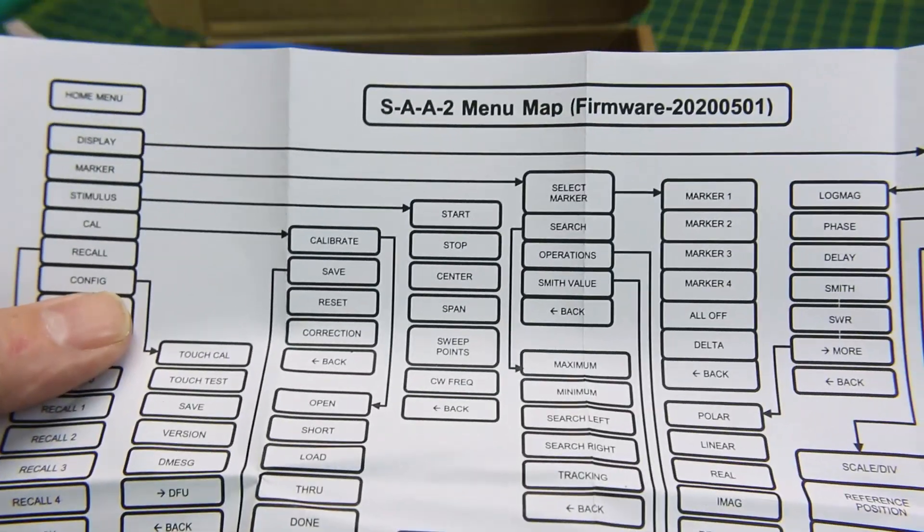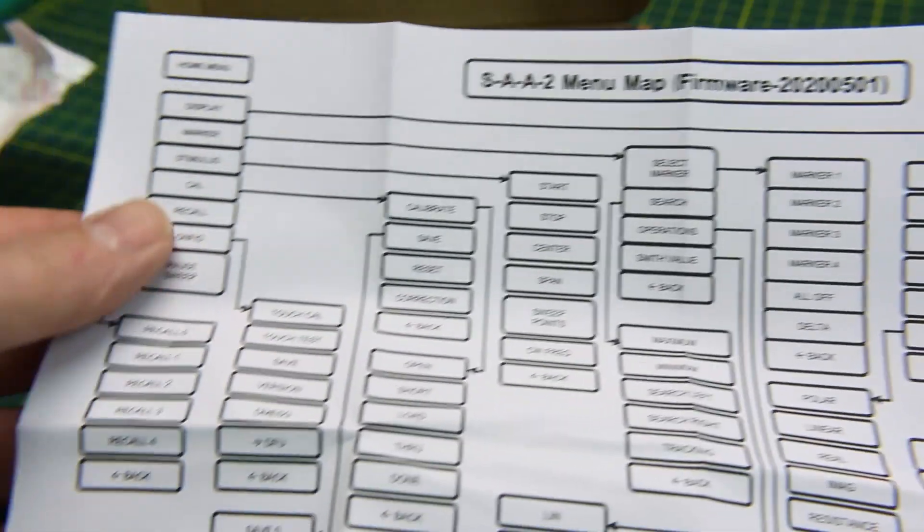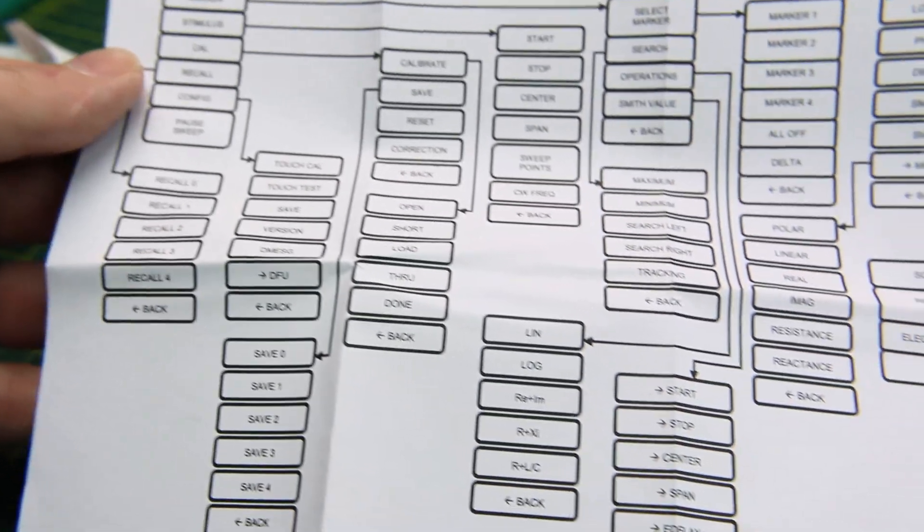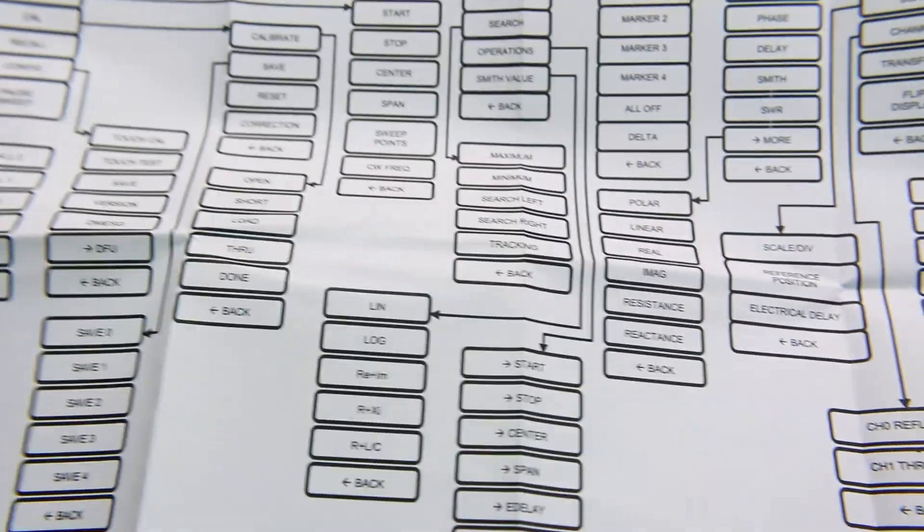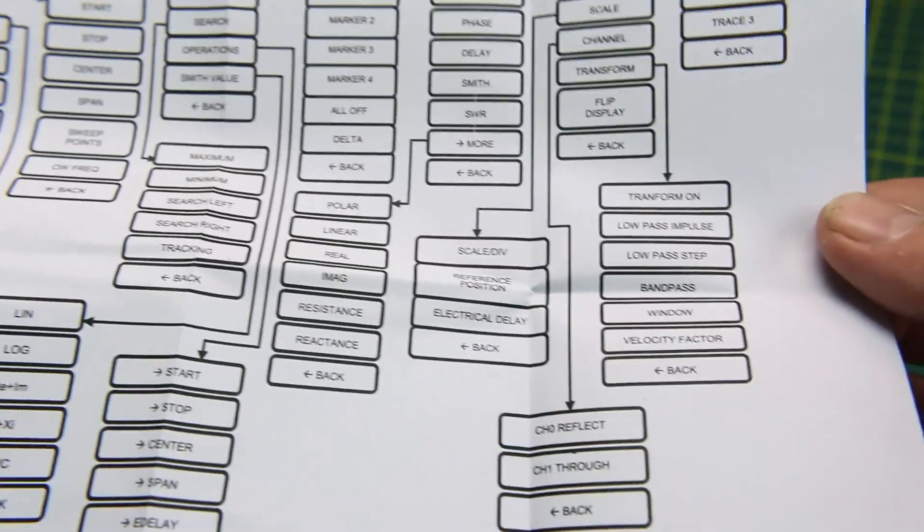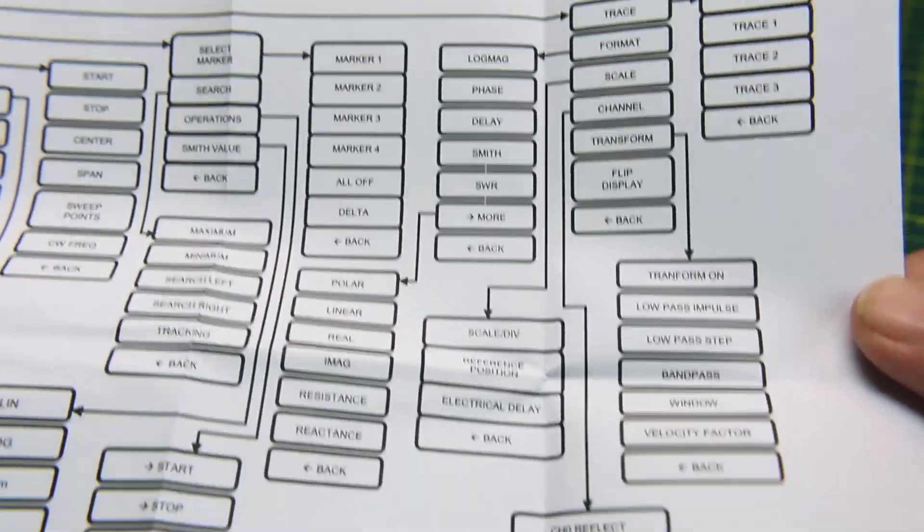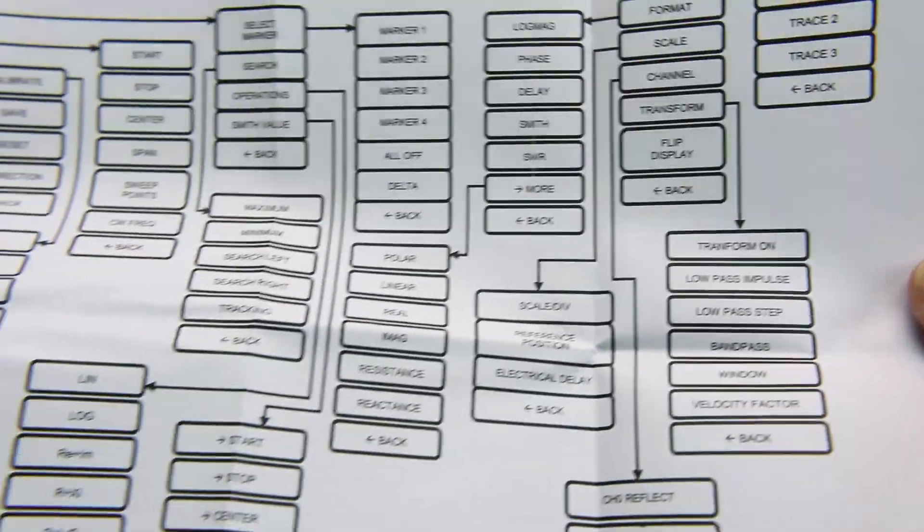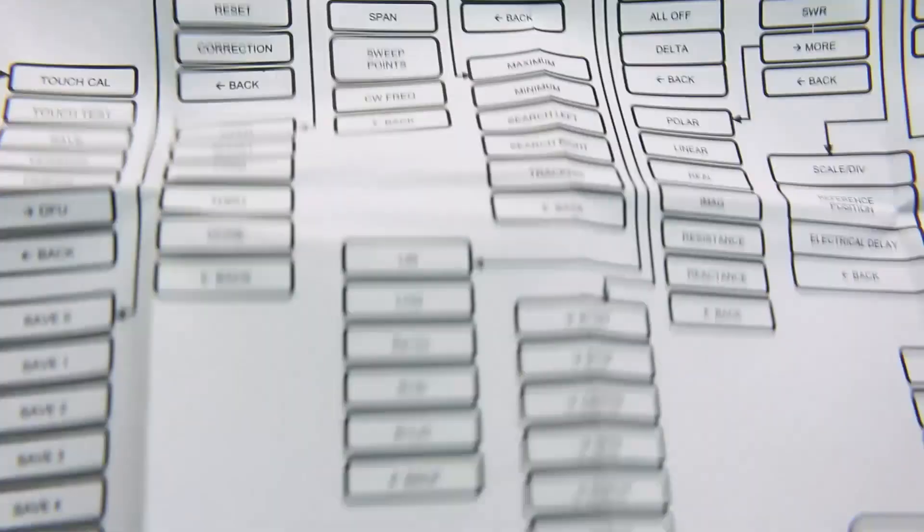You're going to want to hang on to the instruction sheet that comes with it. This is just a layout of the menu structure, and it's really easy once you get your head around the layout, but until then, you may want to refer to this to find the menu that you're interested in. The most common that you're going to need is the calibration menu and then turning off the markers for the different displays.